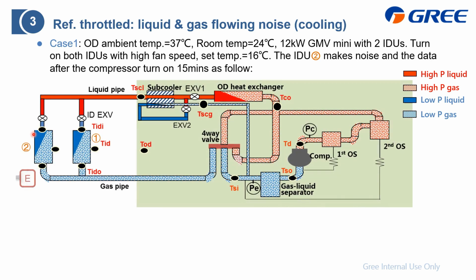And here is the system diagram. Inside the green color is the outdoor unit, and this part is the indoor unit. At the outdoor unit, I will show you how the refrigerant flows in cooling mode. From the compressor, what comes out is high pressure and temperature gas. When it goes through this oil separator, it then goes to this four-way valve. Then, as it is cooling mode, it goes to the outdoor heat exchanger to release heat. Then the gas becomes liquid.